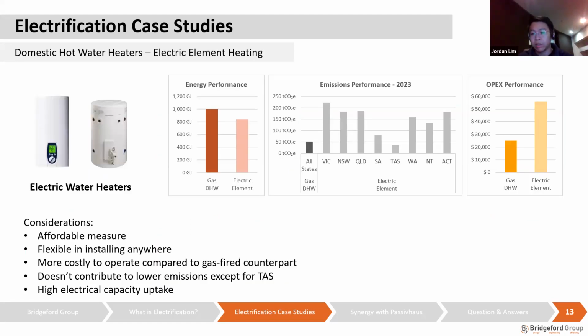I want to first look at the different kind of performance metrics of electric water heaters compared to conventional gas domestic hot water heaters. On these graphs here on the right, you can see that while electric element heating uses less energy in terms of gigajoule compared to gas domestic hot water system, the emissions outcome, depending on the states that you're in, are not very favorable at all, except if you're from Tasmania. That's because Tasmania has the cleanest electricity supply at this day in time. And if we assume a typical gas rate and electricity rate for residential or commercial rates, we are actually paying more for electric element heating than compared to gas domestic hot water.